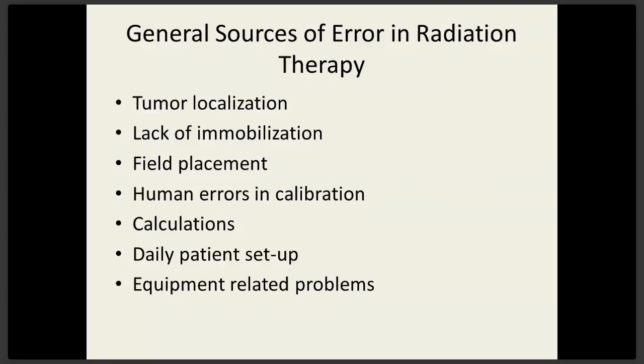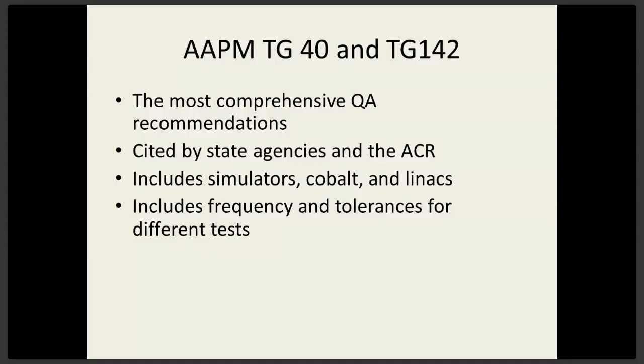So acceptable mechanical tolerances for simulators are usually 2 millimeters. These are conventional simulators. I don't even know why this is up here anymore. Very few people use conventional simulators. TG40 is the most comprehensive QA recommendation cited by state agencies, and includes simulators, cobalts, and linacs. And as I said, it gives you frequency, tolerances, and what to look for.